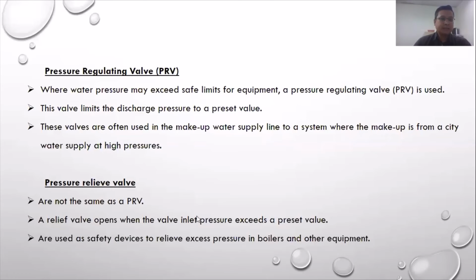Then another, pressure relief valve, is not the same as a PRV. A relief valve opens when the valve inlet pressure exceeds a pressure value. Used as a safety device to relieve excess pressure in boilers and other equipment. So as a pressure relief valve, if the pressure crosses the limit or the maximum, the pressure relief valve will open.